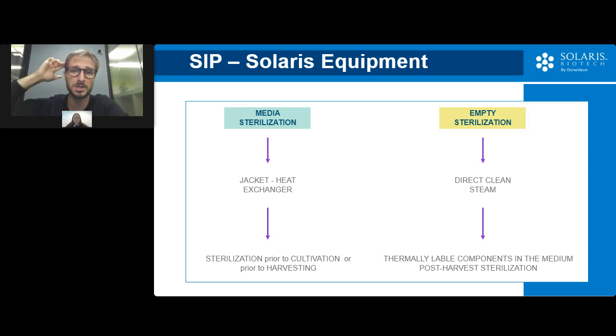During the empty sterilization, clean steam will be directly injected in the vessel. As I mentioned before, it can really come in handy when you have thermally labile compounds. And in this case, the empty vessel gets sterilized, and then the medium will be added afterwards through filtration. Also, the vessel can be sterilized after the harvest phase to inactivate the remaining microorganisms. Again, in case of a BSL-2 or plus or something which is potentially dangerous.